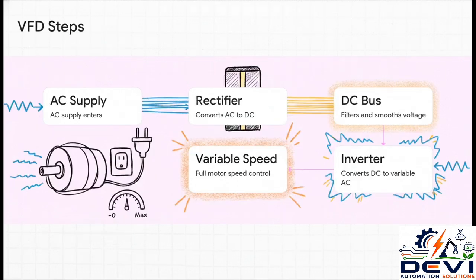And this brilliantly illustrates the VFD process, which is a bit more complex. First, your standard AC supply enters the drive. Second, the rectifier section gets to work converting that AC power into DC power. Third, the DC bus takes that DC voltage and filters and smooths it out. Fourth, and honestly, this is where the magic happens, the inverter section takes that nice, smooth DC and converts it back into a highly controlled variable AC power. Which brings us to step 5, completely variable speed motor output. You have absolute control from 0 all the way to full speed, and sometimes even beyond.